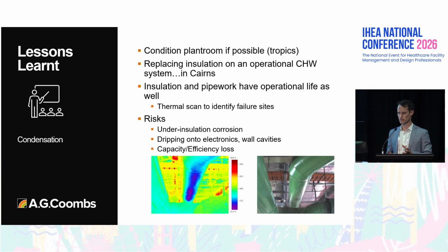I'm a big advocate of conditioning plant rooms in the tropics if we can—understanding this was an existing plant room—but it does get around a lot of the issues you see on a regular basis. You can't lag everything to the point where you'll never get condensation forming. There's always going to be binders or valve handles or something that's going to sweat, and that could be dripping on electronics or controls, or tracking underneath the insulation and causing pinhole leaks.